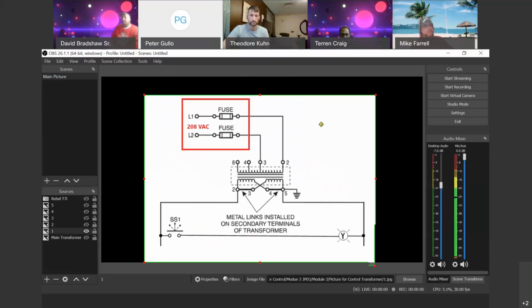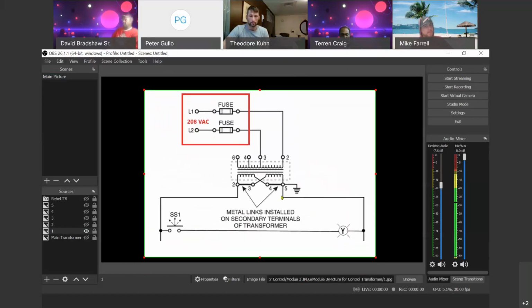See the new screen? We talked about this. We constantly talk about this. Marinate on this. Go to bed that night and dream about this. L1 and L2, 208, going to the fuse, all the way down to where? The 208 should be seen where? Pin 2 and 3 of the transformer. That 208, if everything is running good, should be down there on the transformer, primary side. The only thing I'm missing here is I forgot to put the L on the selector switch, guys.